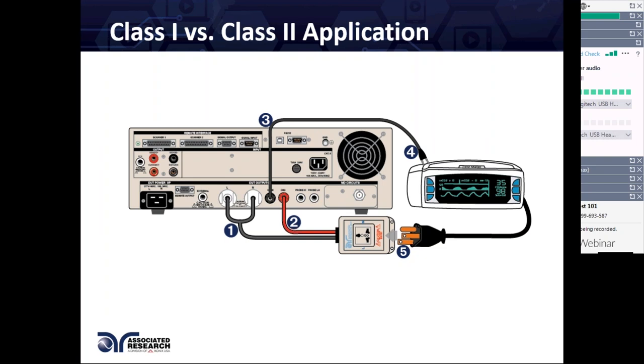Usually it's a series of tests: for a class 1 product, you start with continuity or ground bond, then move into high-voltage testing — Hypot and insulation resistance — and then move into leakage current testing. Depending on the application, you can use different configurations for Hypot testing.